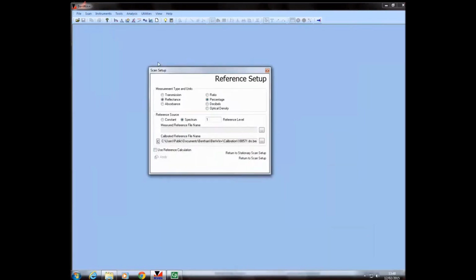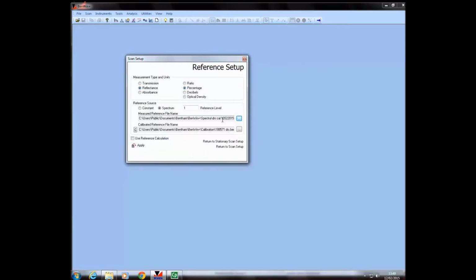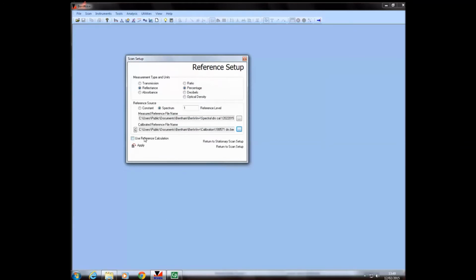And to implement correction, we go to Scan Reference Setup. Firstly, you should load the reference source, which is a spectrum. It is the DRS cal file we've just saved, and the calibrated reference file name has already been loaded here, but is provided in the calibration folder, and is this file here, which relates the calibrated reflectance of this particular standard. We can choose reflectance as the type of measurement and the units, use reference calculation, and hit apply. Returning to scan setup, we are now ready to measure the spectral reflectance of our monocrystalline silicon cell.